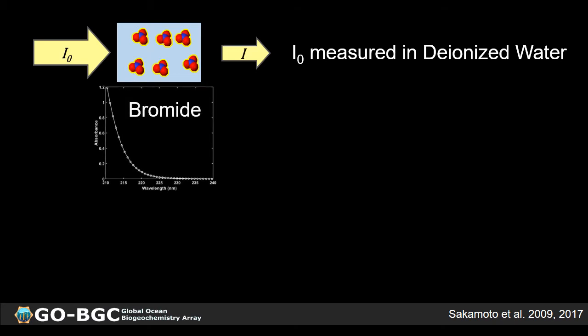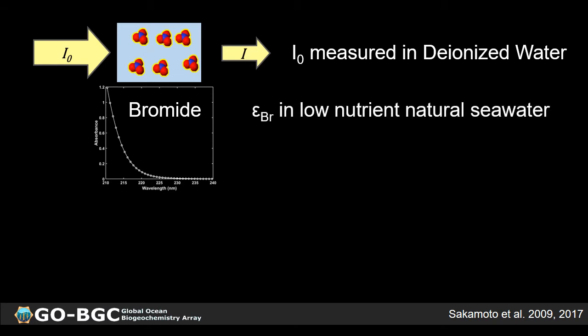The second component we need to quantify for each sensor is the bromide spectra. Basically, for each instrument, we measure the molar absorptivity of bromide in low nutrient natural seawater. So we measure the salinity of the natural seawater and calculate what the bromide concentration should be, and then quantify the molar absorptivity for bromide for each sensor. And we define the molar absorptivity in a way that makes it easy for people to calculate what the absorbance of the bromide would be. Basically, in order to calculate what the absorbance is, you multiply the molar absorptivity of bromide by salinity, and then correct it for temperature and pressure. So in other words, the molar absorptivity of bromide that's determined in the calibration process is basically what the absorbance of bromide would be when salinity is equal to 1.